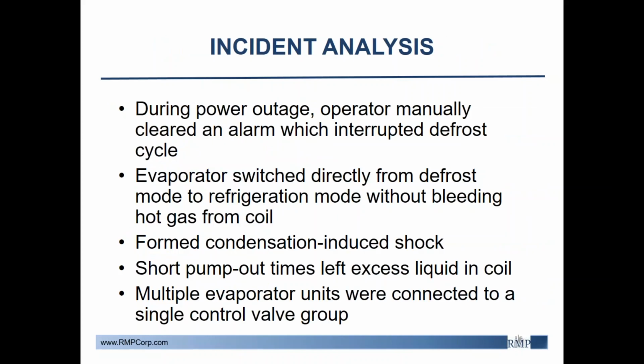The MILLARD incident was caused by multiple factors. While troubleshooting issues during the power outage the previous day, an operator manually cleared an alarm, which resulted in an interruption of the defrost cycle in progress for a blast freezer evaporator. The evaporator switched directly from defrost mode to refrigeration mode without first bleeding the hot gas from the coil. Bleeding the hot gas is necessary to prevent a rapid reduction of pressure in the coil when the low temperature stop valve opens. The manual intervention reset the control system, so it did not recognize that the unit contained high-pressure hot gas before allowing the suction stop valve to open.